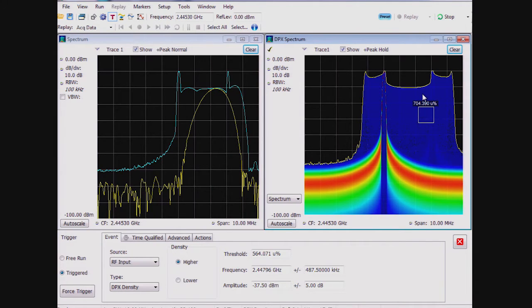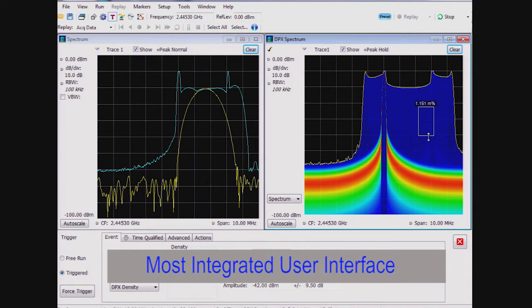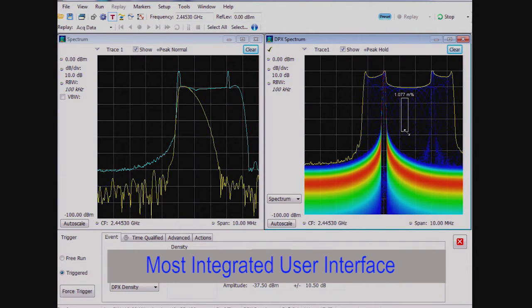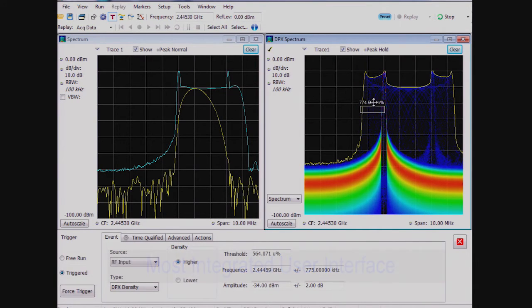This DPX density box is adjustable by the user. This trigger lets you trigger on any of the signal that you can see on the DPX spectrum screen by positioning the box and adjusting its size. This is easy to do with the mouse graphical user interface in the RSA.